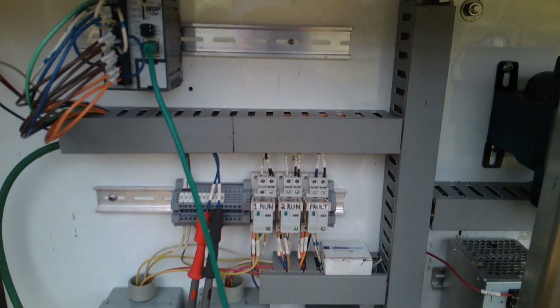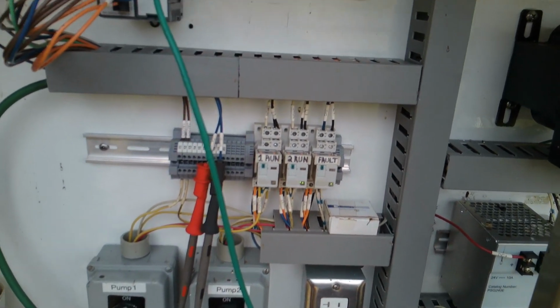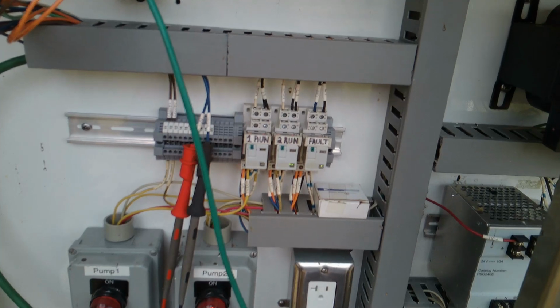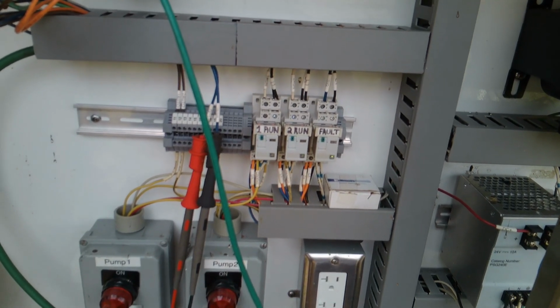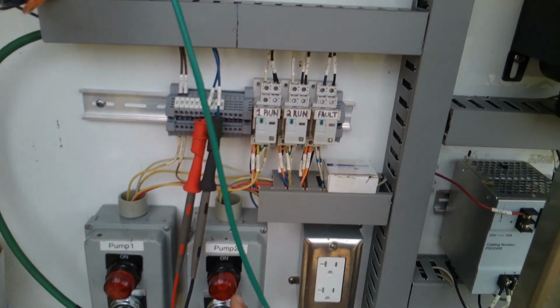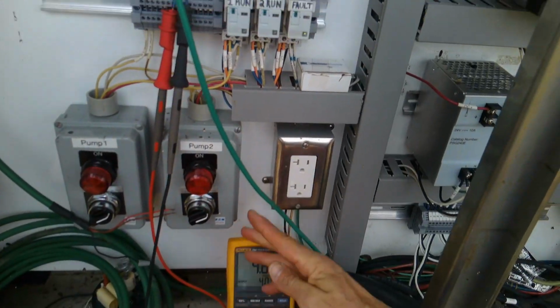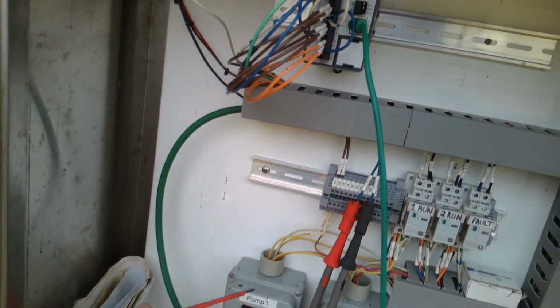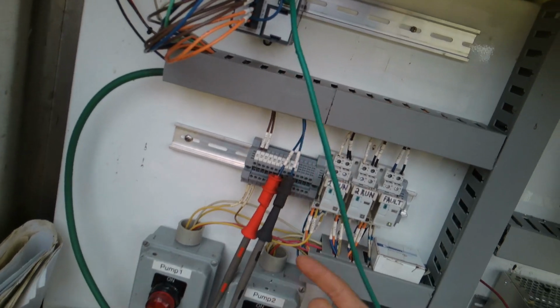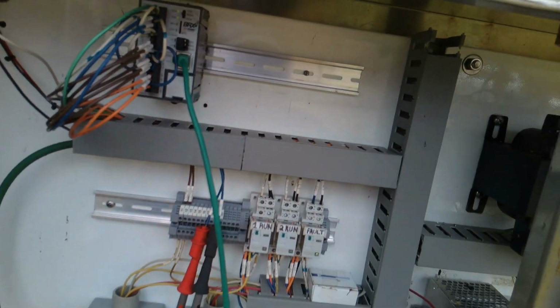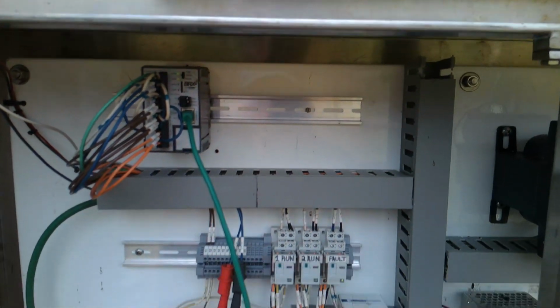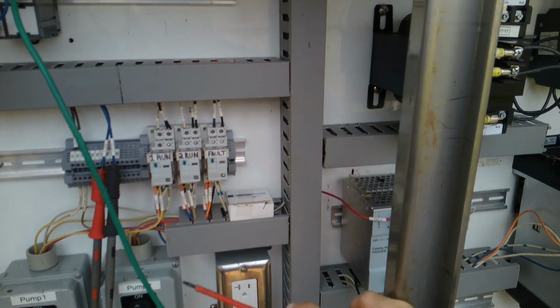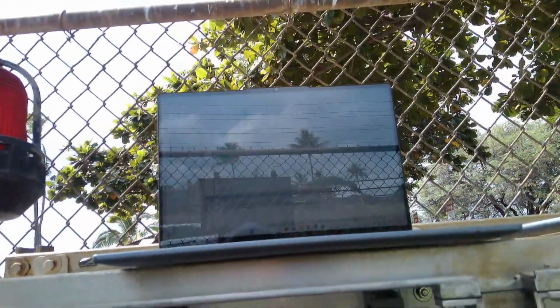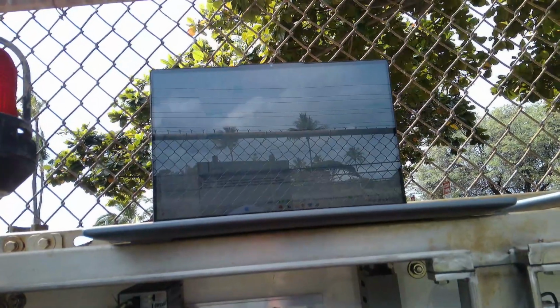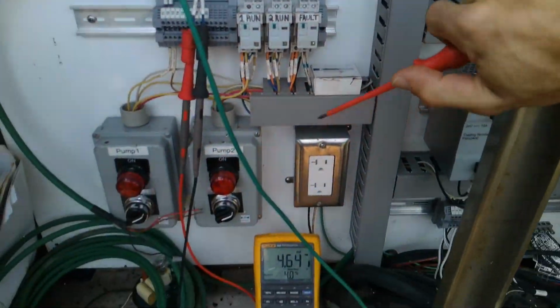6.5%. 8,000. There, now pump 2 kicks on at 7%. So that's all it has to do is jump up above 7%, drop down to 4%, then the pump will turn off. And then if it jumps above 7% again, pump 1 will come on, then pump 2, and if it jumps even higher, they'll both turn on. So in the eyes of the computer, it's getting a level that's going up, down, up, down, up, down, rapidly. Okay.